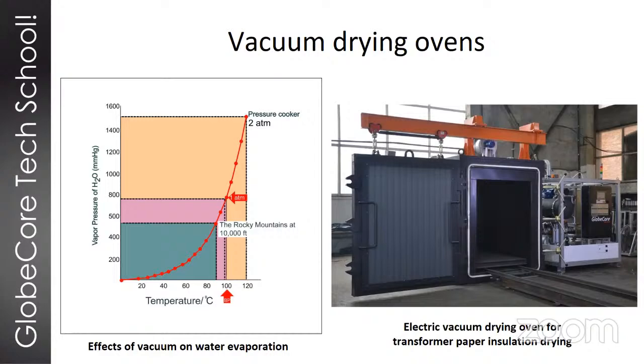One limitation, perhaps, of this method is the need to open the transformer and extract its core, which only then can be installed in the chamber of this oven. And this is not something you can do in the field. So the transformer has to be transported to the shop. It has to be maintained and serviced at the shop where the chamber is located. However, if you have a chamber of adequate size, you can use it to dry a transformer of just about any size. In general, such drying in vacuum chambers does require quite a bit of energy, which is expended to heat the solid insulation inside the oven. Basically, this process is quite energy intensive. It requires a lot of energy. Next slide, please.